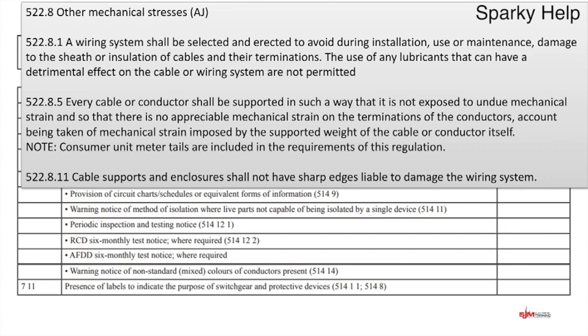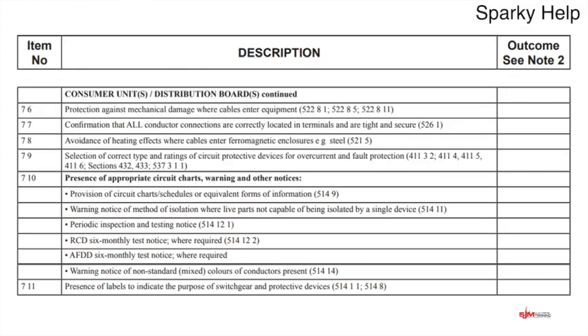Cable supports and enclosures shall not have sharp edges liable to damage the wiring system. Obviously the whole point of an enclosure is to protect the cables, not damage them. So if we've fundamentally failed at that, we've done something wrong. So that one should be a tick. Confirmation that all conductor connections are correctly located in terminals and are tight and secure.